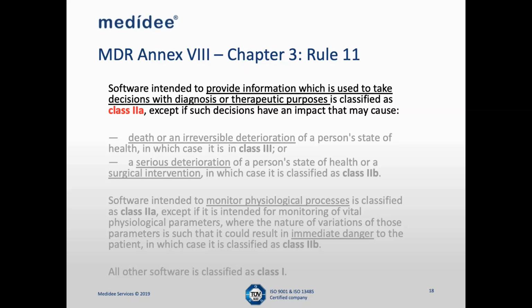Considering the genericity, this particular rule will generally be applied to the majority of software, excluding only those software that have no medical purpose, which can be classified as Annex 16 products. But if you have a medical device software which is intended to provide information or to take decisions with diagnosis or therapeutic purposes, it is generally envisaged to be in class 2A.